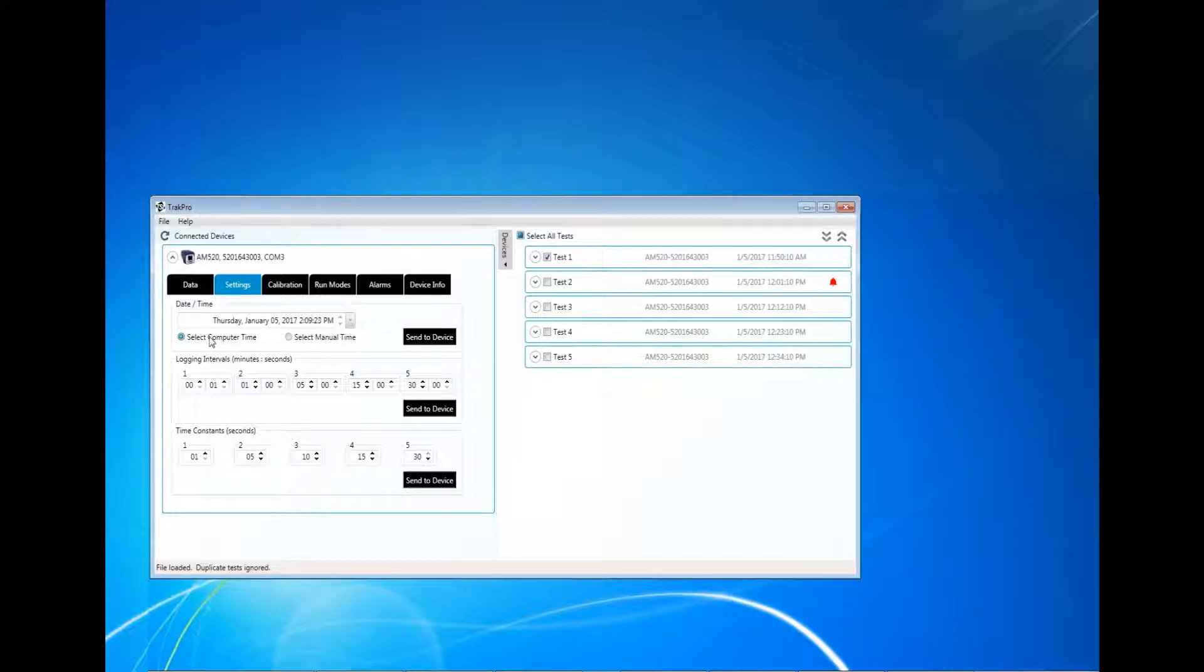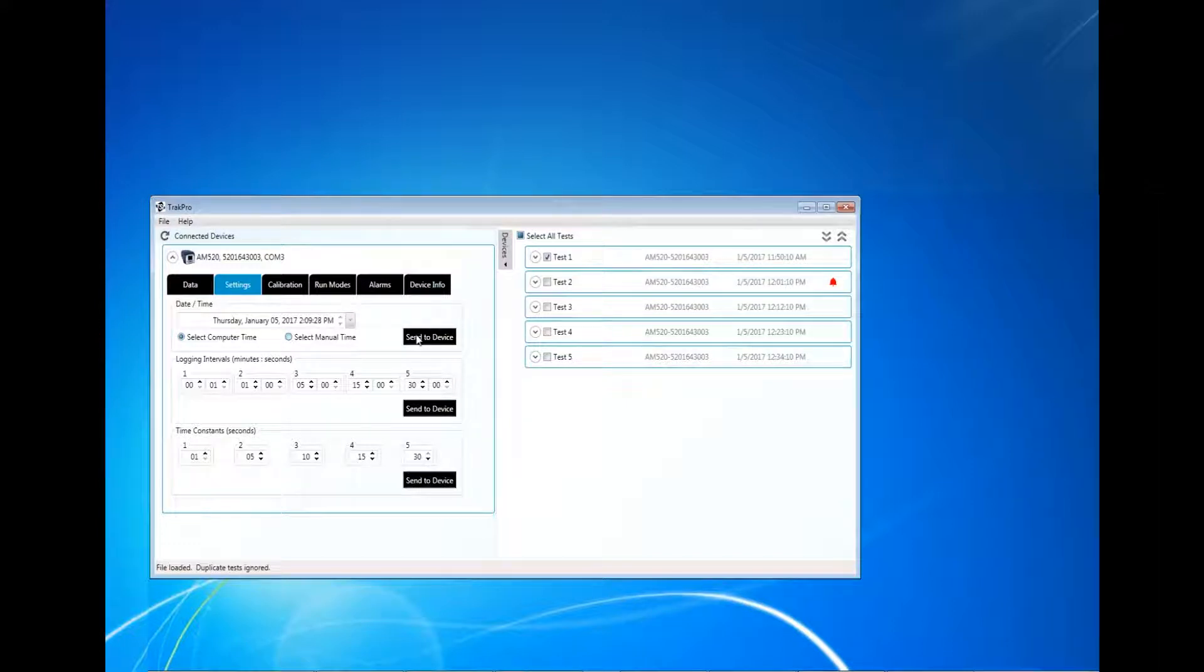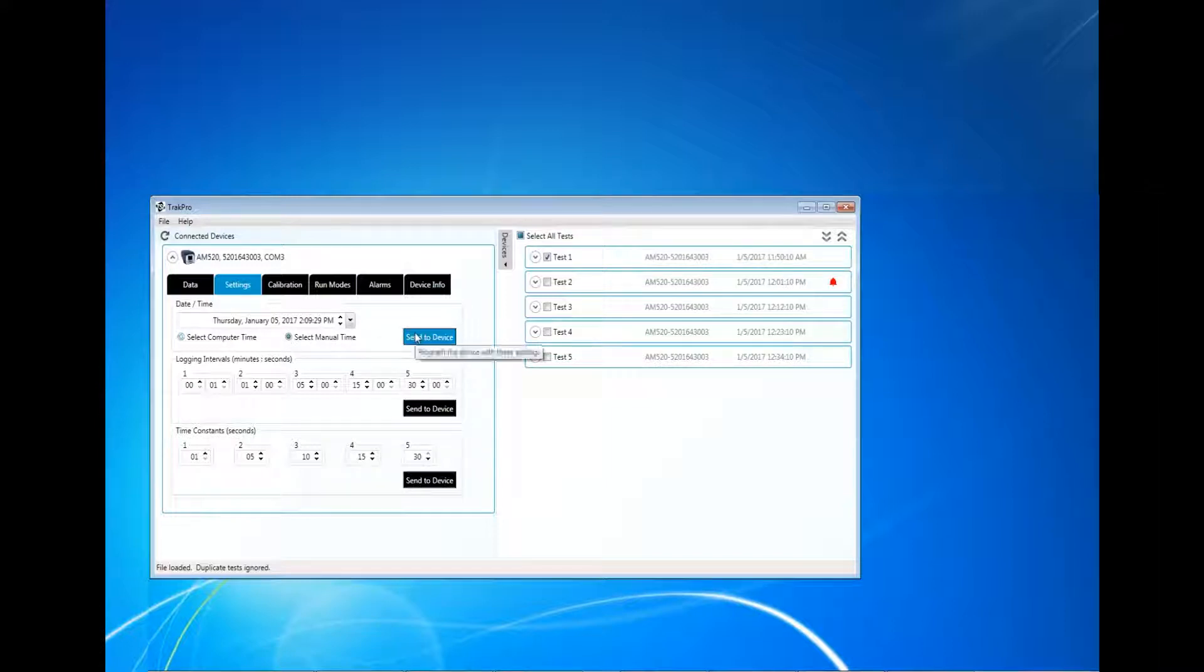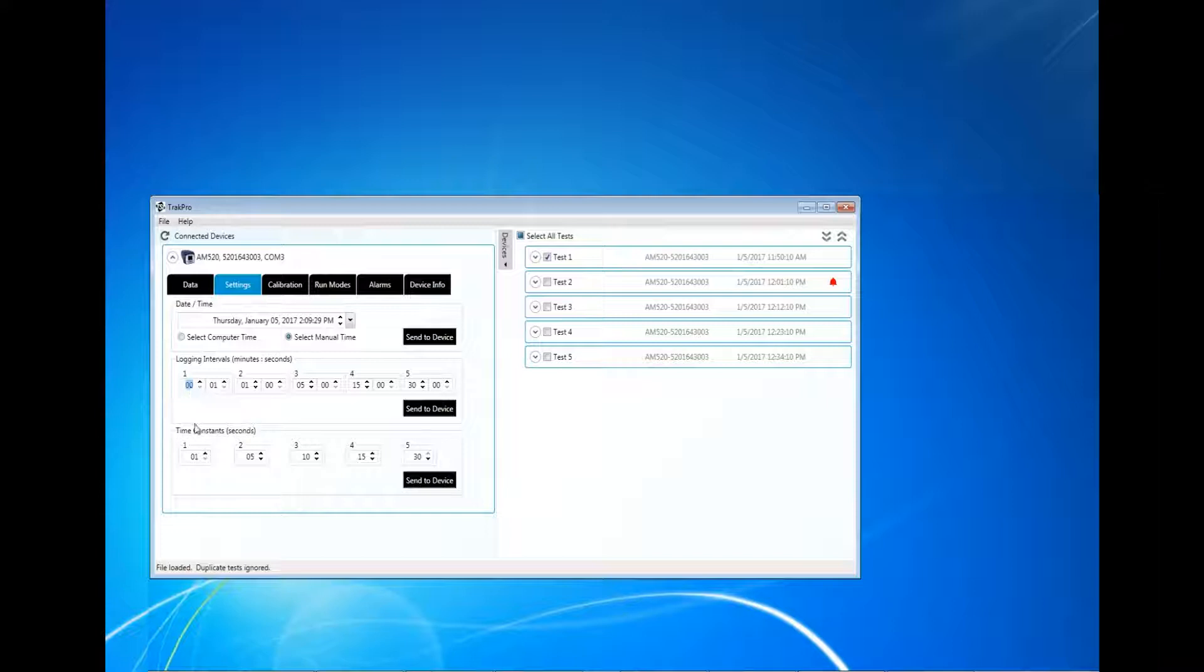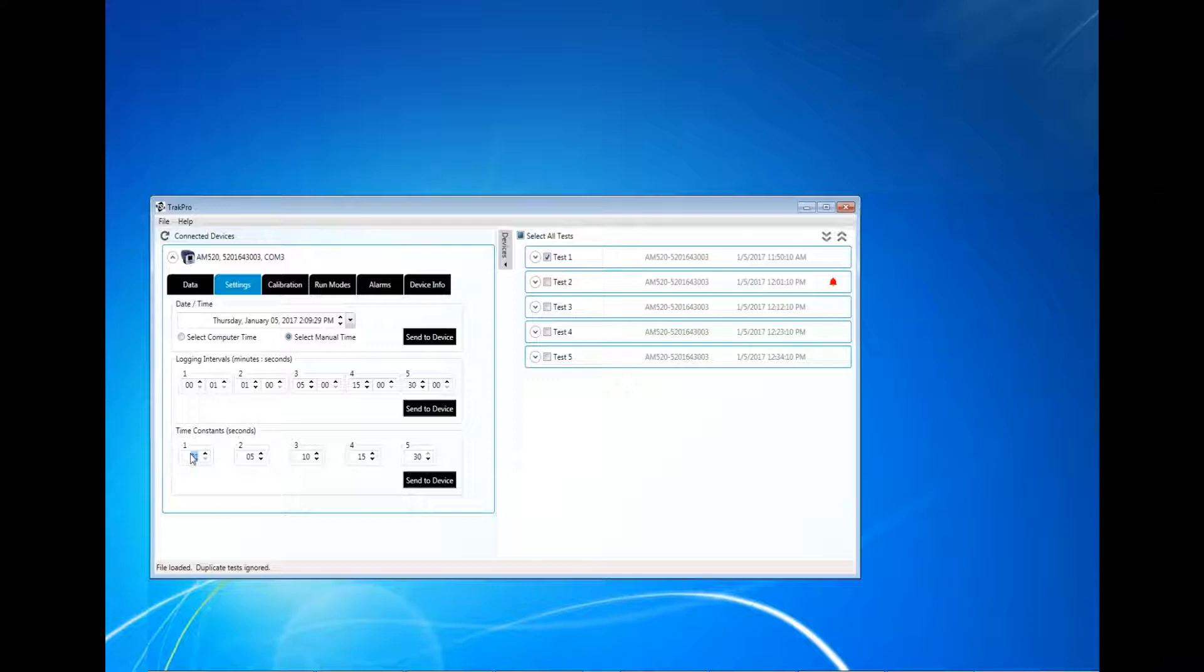Five different logging intervals can be configured and sent to the instrument. These will be used when the instrument is in the manual run mode. Five different time constants can be configured and sent to the instrument. The time constant will dictate how often the mass measurement reading will update on the LED screen. Refer to the AM520 user guide for further clarification.